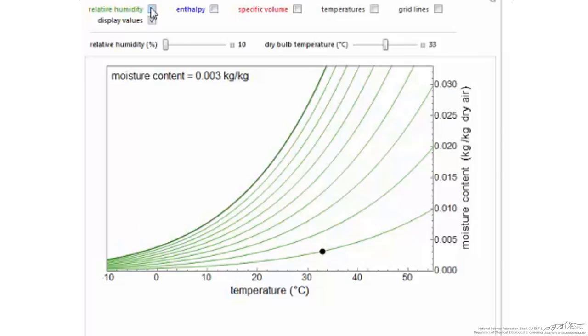I will now start adding details to the chart. First, we will show the percent relative humidity. We are at a low 10% RH for these conditions. Relative humidity varies between 0 and 100%. The saturation line is the curved line on the left of the plot and represents 100% RH.